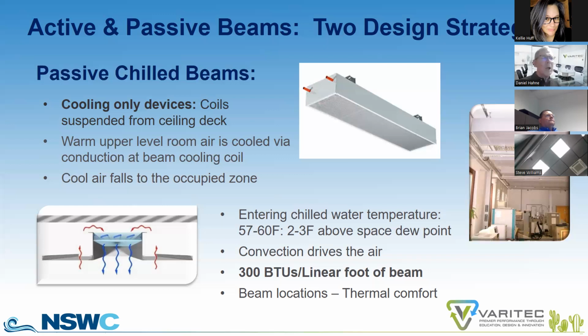So if you have a room at 75 degrees dry bulb, 50% RH, you have a 55-degree dew point, you want to provide your air, or your chill water, at roughly 57 to 60 degrees to make sure that the chill beam does not condense at the beam.